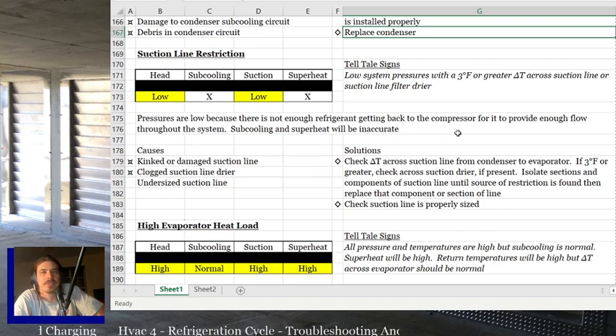Otherwise, if you have weird problems, like if it looks like an undercharge and you try and charge the system and nothing seems to be fixing it, you know what I mean? You add charge and everything's still kind of low. None of the pressures are really moving. It doesn't look right. Check your line. See if you got a greater than 3-degree temp difference. See if the suction line's grossly undersized. See if they put a 3/4 liquid line on a 5-ton. You know what I mean? Look for weird things like that because you could have a suction line restriction.